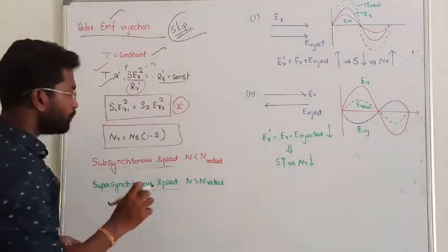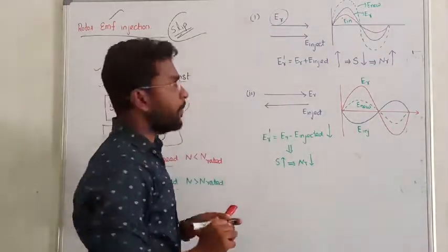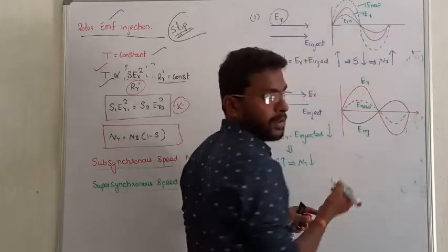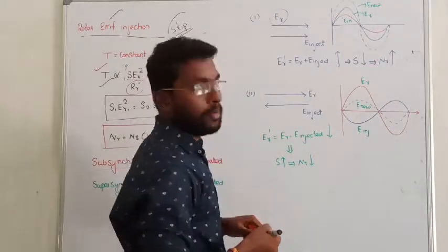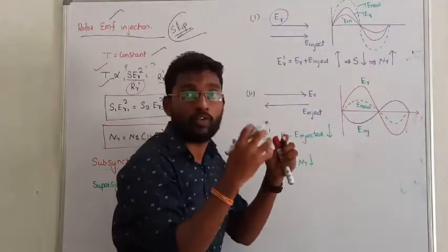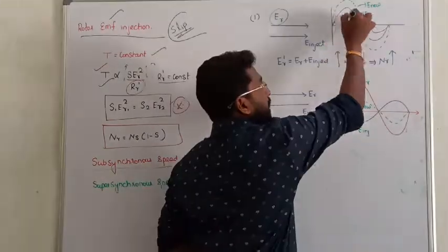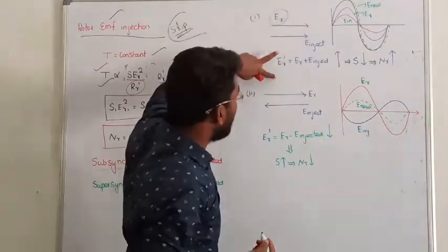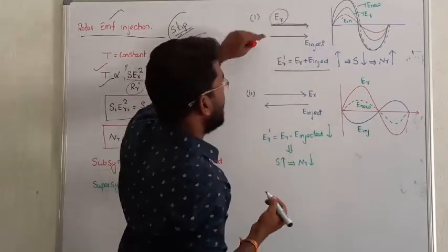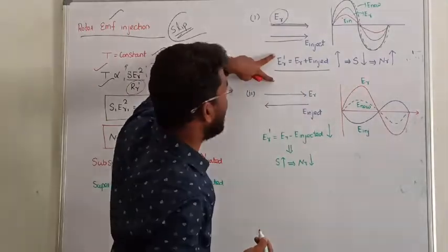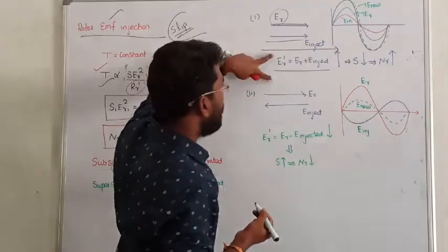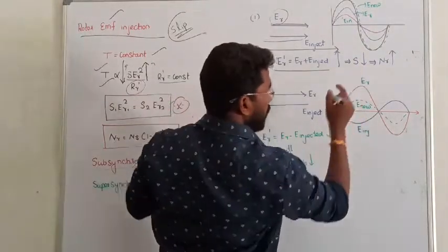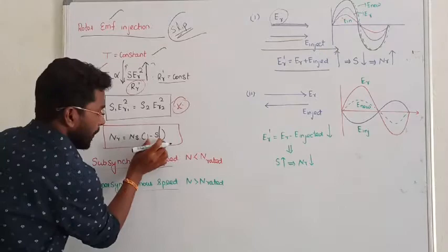Let us take case number one. Assume this is my initial rotor circuit. The rotor already has some induced EMF — shown in blue color, this is my induced EMF. If we inject some additional EMF from an external source into the rotor circuit in the same phase direction, the two EMFs add up. The resultant EMF value of the rotor increases beyond the rated value. To maintain the torque constant, we must reduce the slip. As slip reduces, the rotor speed will obviously increase — that is called super-synchronous speed.